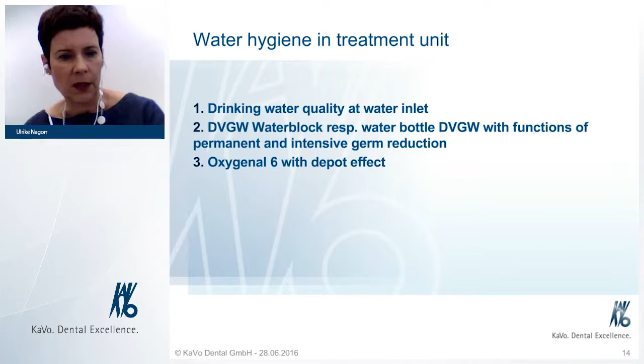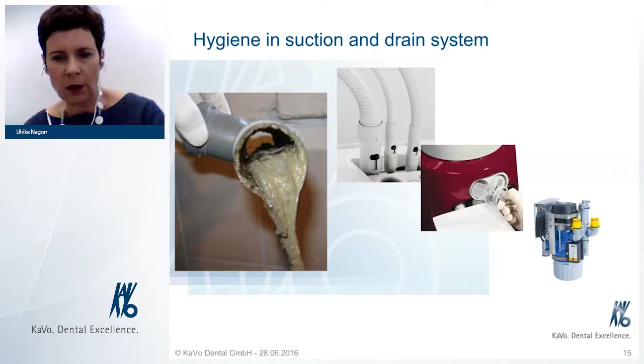So another important topic is the hygiene in the suction and drain system. Sometimes you might have seen in some situations pictures like that when the service technician has to check some clogged, blocked suction lines. And if we speak about suction, of course we have in mind the suction tubings, the high volume suction, the saliva ejector. We have in mind the suction sieves or filters and the suction machine itself, independent of whether it is a dry suction machine or a wet suction machine. This is not the matter. Both of them need to be maintained in the right way.